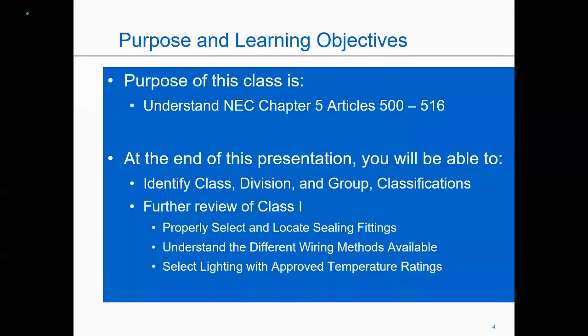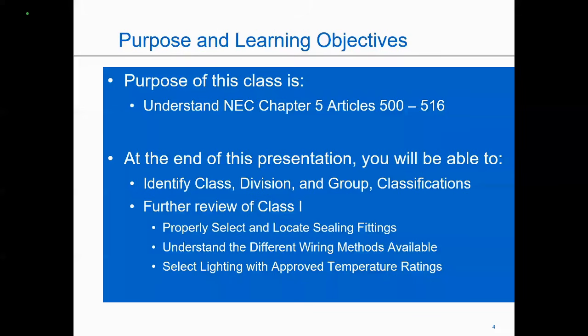After we do a little bit of the basics overview, we're then going to take a further dive into class 1, the areas with the flammable gases, liquids, and vapors. For those of you that might be interested in class 2, we do have another presentation that does a deeper dive into the combustible dust. But as we're discussing the class 1 areas, we're going to look at the location of sealing fittings. We're going to look at the different wiring methods that are available. And then we're also going to look at lighting and temperature rating concerns when selecting our luminaires.